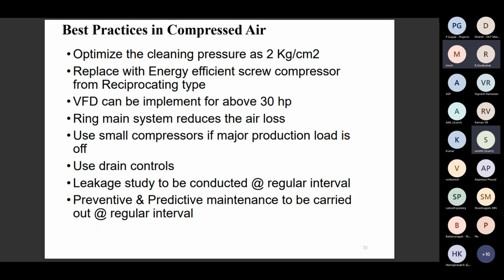Next, replace reciprocating compressors with energy efficient screw compressors. Still, many small and micro industries are using the reciprocating type. For reciprocating type, the FAD is very low, because it generates nearly 3.5 CFM per HP only, whereas the latest energy efficient IPM, internal permanent magnet motor, compressors generate nearly 5.5 to 5.8 CFM per HP. So the old reciprocating compressor can be replaced with a screw compressor. And a VFD can be implemented above 30 HP wherever there is a loading and unloading problem.